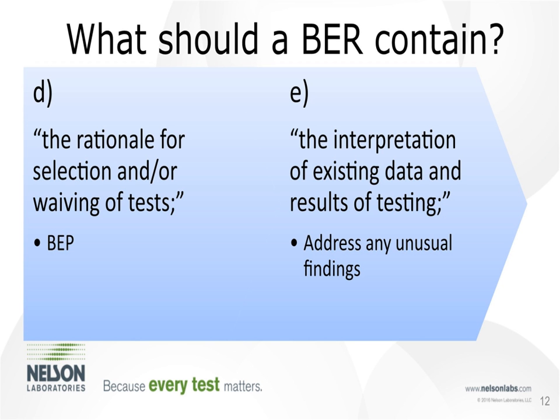Part D covers the rationale for selection and/or waiving of tests. This references back to the biological evaluation plan and is determined by the device categorization based on contact type and duration, as well as any parallel standards identified that need to be followed for the type of device and patient contact.